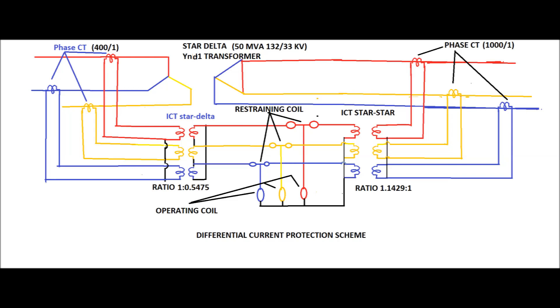A schematic diagram for the operation of a differential current protection scheme for a three-phase power transformer operating at 50MVA, 132/33kV, YNd, has been shown in this figure. The CT ratios used on the HV side are 400/1 and on the LV side 1000/1. ICTs are used on either side of the transformer for phase and amplitude matching so that under normal load condition, the relay current for both windings shall be the same. The ratio of ICTs on the star-delta side is 1 to 0.5475.